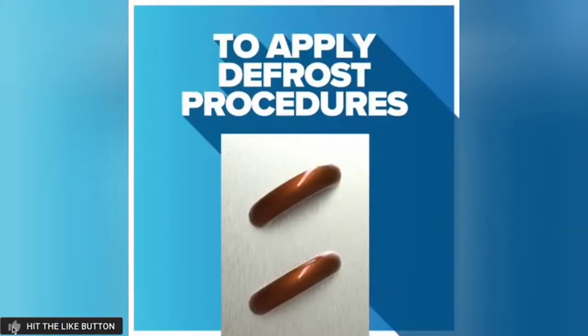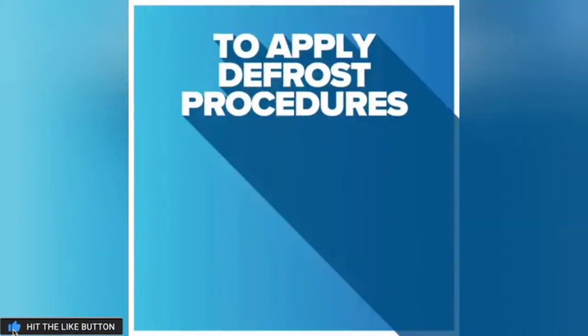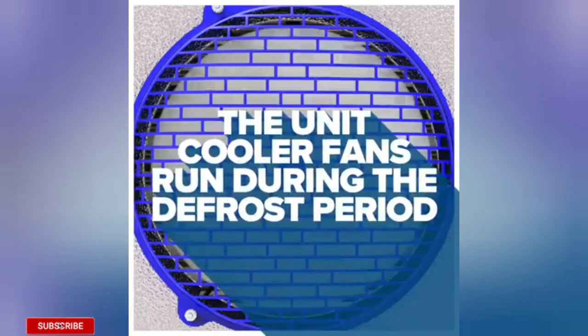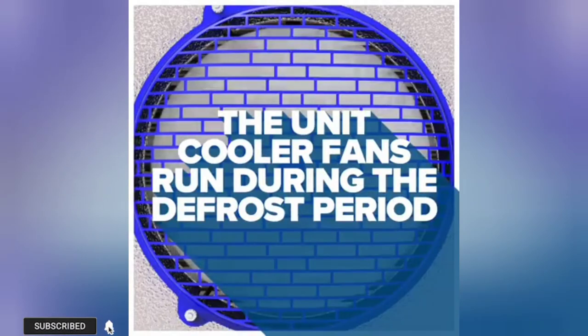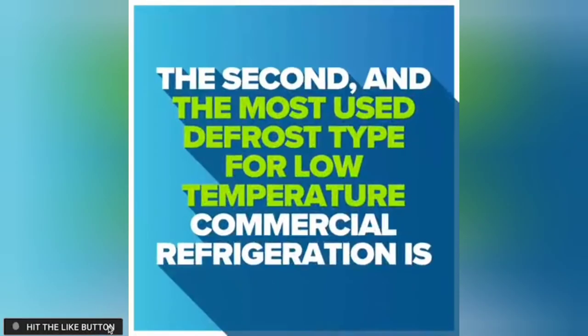To avoid excessive frost from obstructing airflow through the evaporator coil, the system stops the compressor and outdoor fans periodically to apply defrost procedures. This is air defrost. During this type of defrost, the unit cooler fans run during the defrost period.